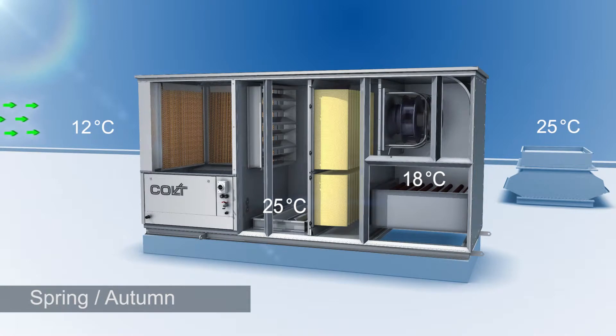In the autumn, heat recirculation kicks in. Outside air is mixed with warmed inside air. This pleasantly tempered mixed air is filtered and brought into the building. The total supply of air is matched to what is actually needed, thereby saving significant electricity costs.